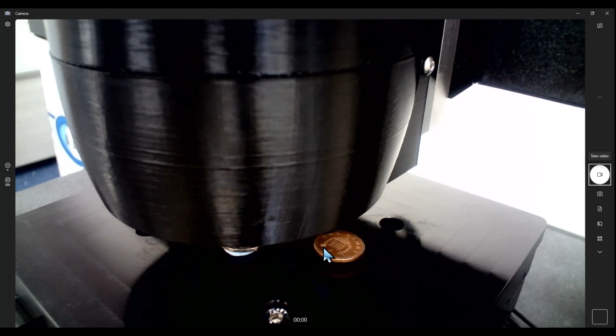I know I'm in the measurement mode, and if we look at the overview camera, I think you can just about see a point of light here on the surface, which is roughly where the chain is coming down the coin. So let's just minimize that picture and leave it over the top so we can see what's going on. I'm in a measurement mode, as indicated here. I'm going to collect a measurement area 3 millimeters by 3 in the area we selected from the microscope. And I'm collecting 101 data points, so it's 100 spaces by 100 spaces, which gives us a spacing of the data of 30 microns. All I need to do now is click measure.